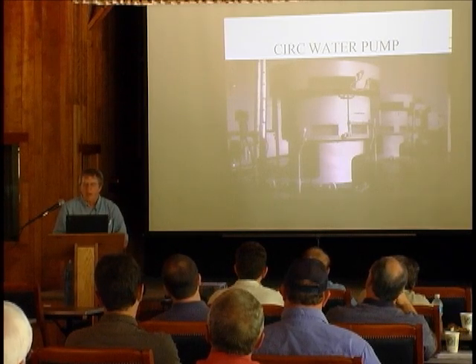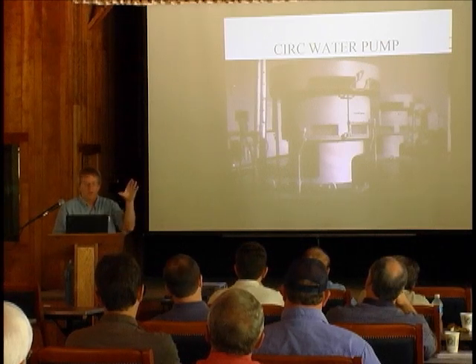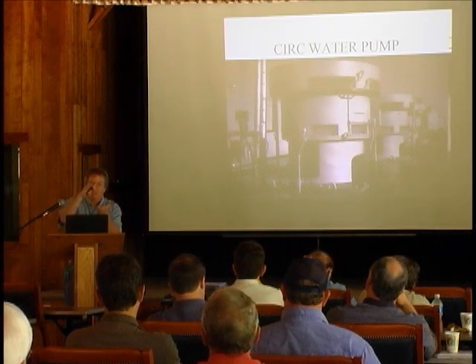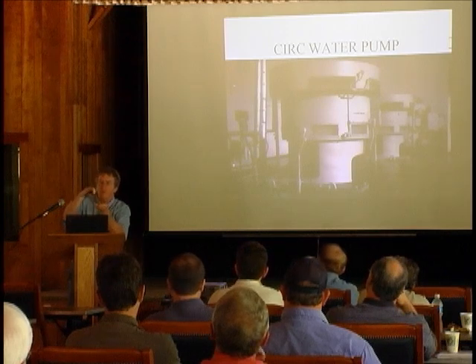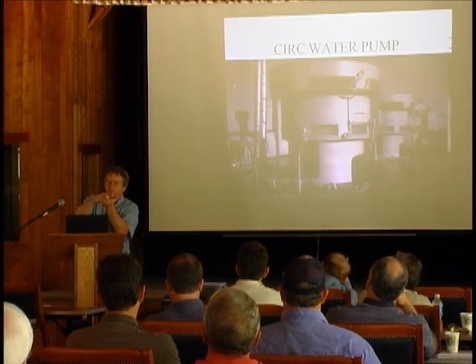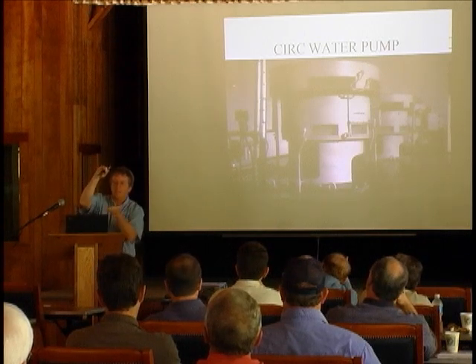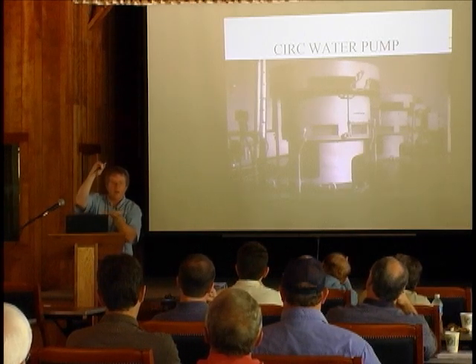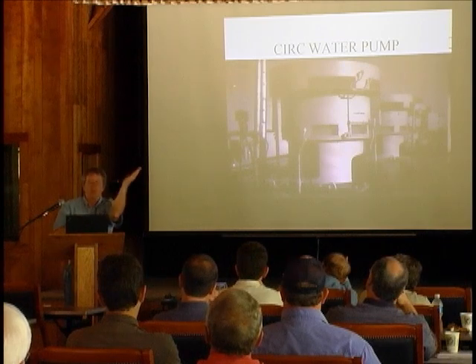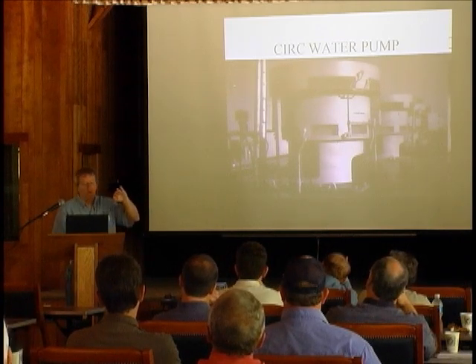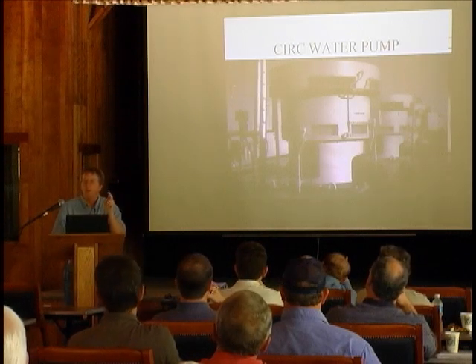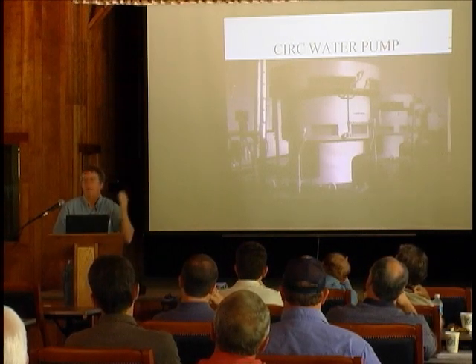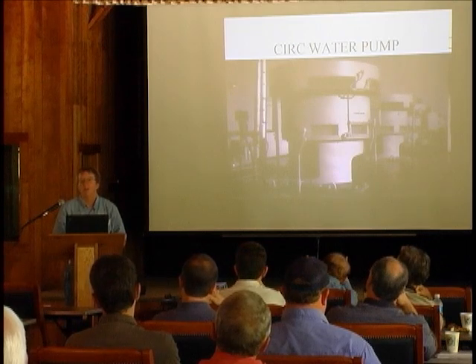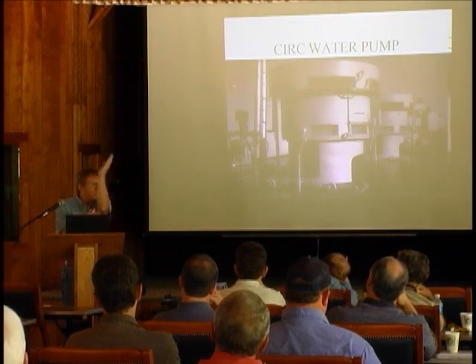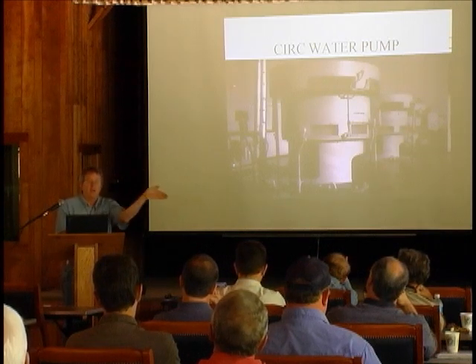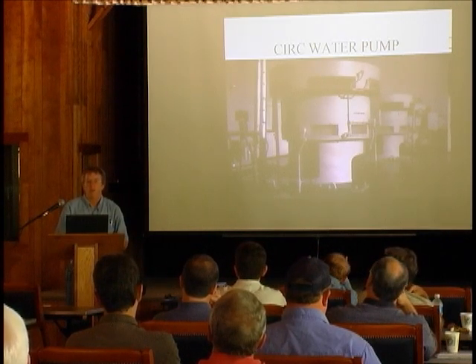And that angle, with the outward component, is dependent on flow: no flow, high flow, and then that adds to this vector. And so you create an angle that varies from here out to here. Your diffusers are set at a certain angle, so only at one flow does that angle match. And whenever you get too much back pressure, the flow component drops, the angle coming off the impeller drops, and it's hitting at too shallow an angle, and you get vane pass frequency.